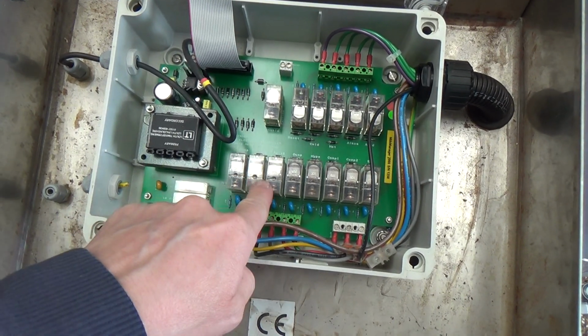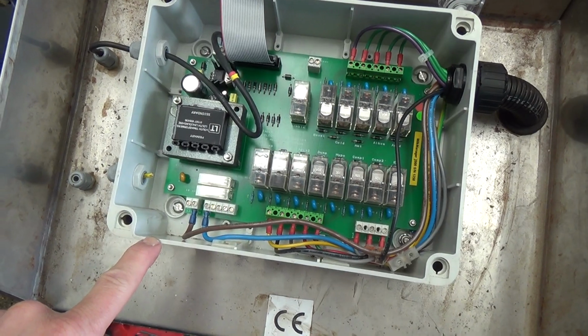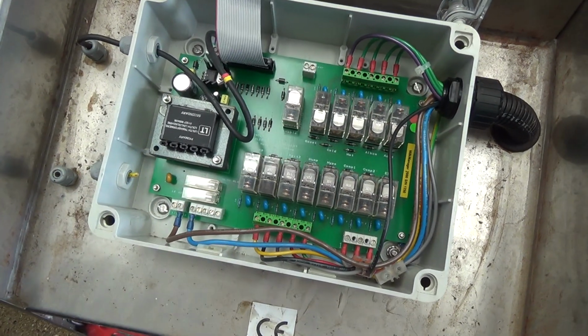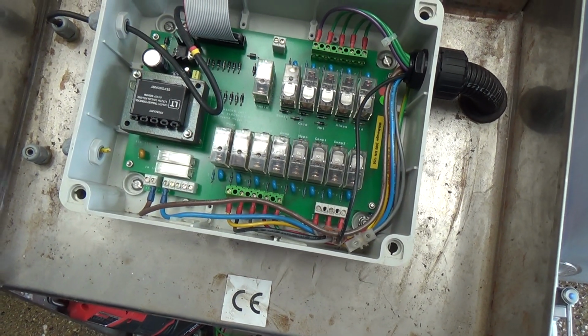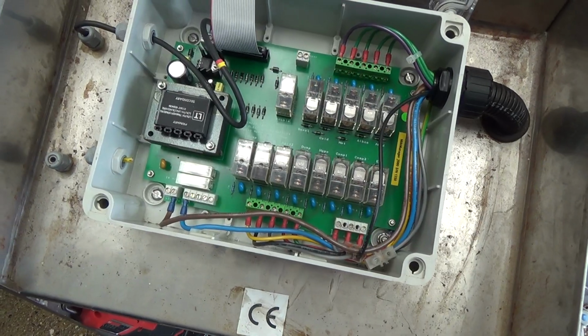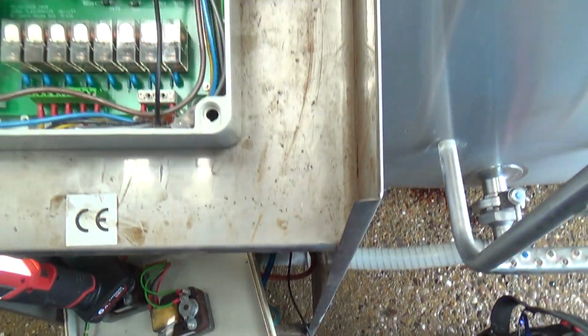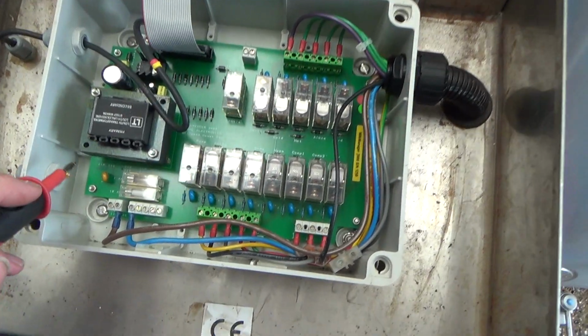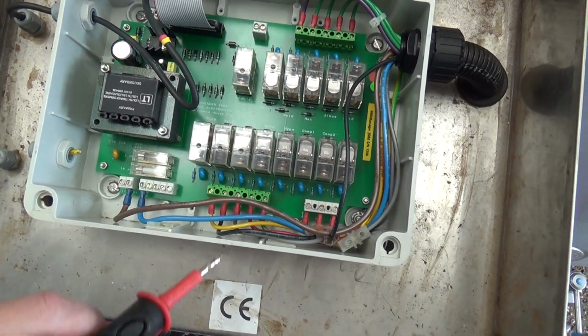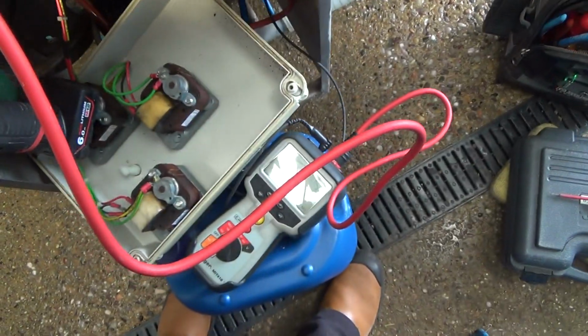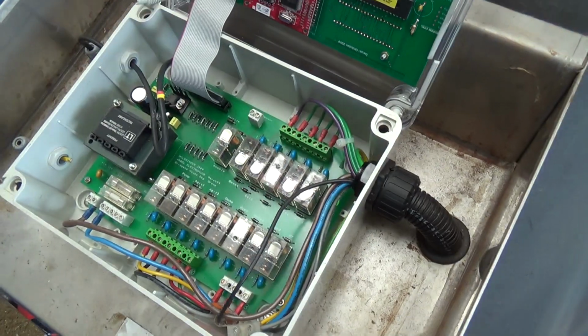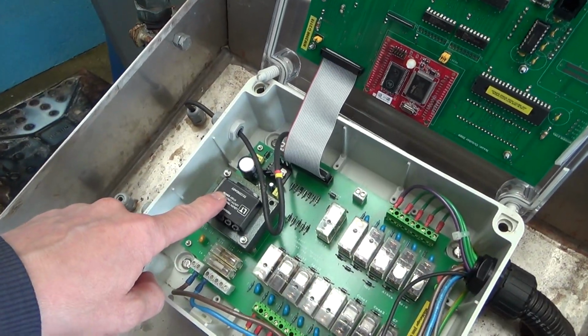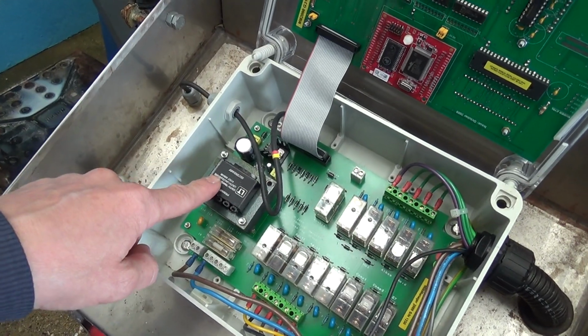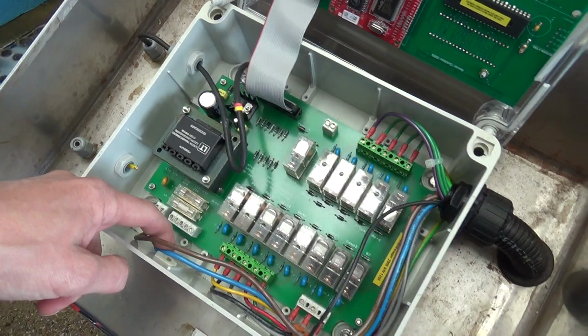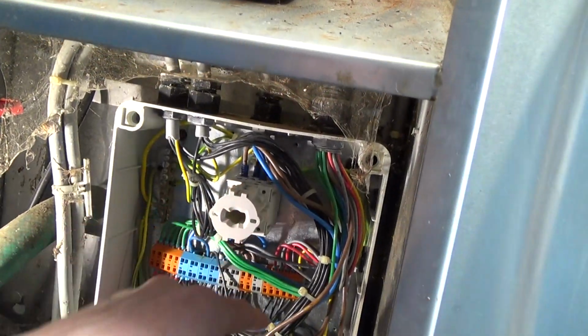I don't think any of these relays are stuck in. Unless there's something on the underside of the board. This is weird. This is a weird one. What should we do? Should we try the neutral? No, that's shorted too. Right. We might just be going up the neutral then. You might be going up the neutral because that's probably going to go through the transformer. Because I suspect that's just across the live and neutral incoming. And we tried the neutral down here and we didn't have anything on it, did we?